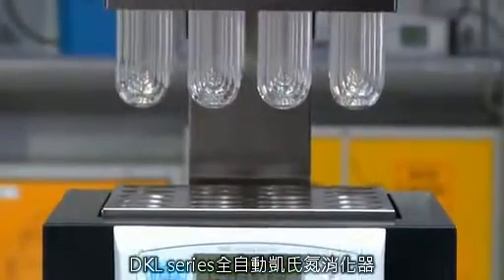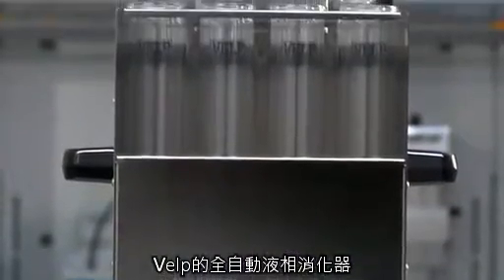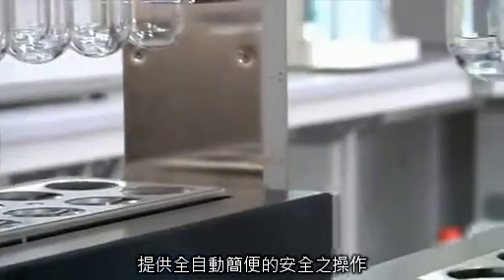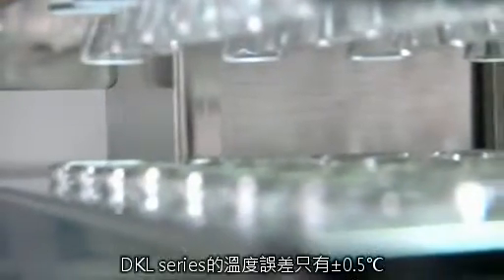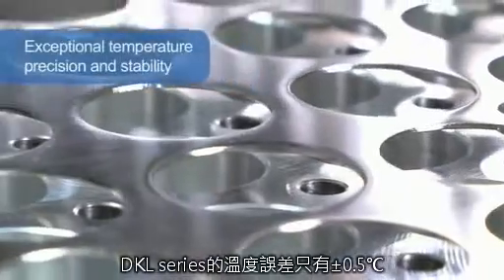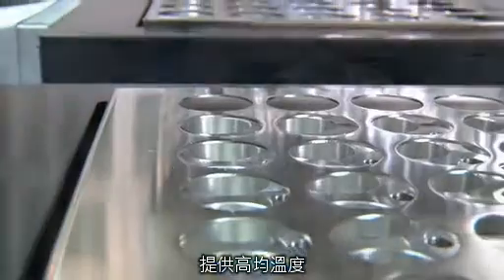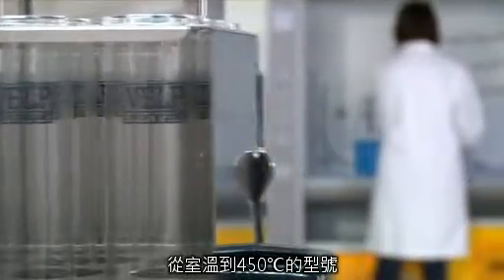DKL Series Fully Automatic Kjeldahl Digestion Units. The new automatic Kjeldahl digesters from Velp Scientifica provide users with the ultimate technology whose objective is to simplify operation, improving the safety. The DKL Series offers exceptional temperature precision and stability, only plus or minus 0.5 degrees centigrade for all the samples, allowing complete and homogeneous digestion and covering a temperature range from ambient to 450 degrees centigrade.